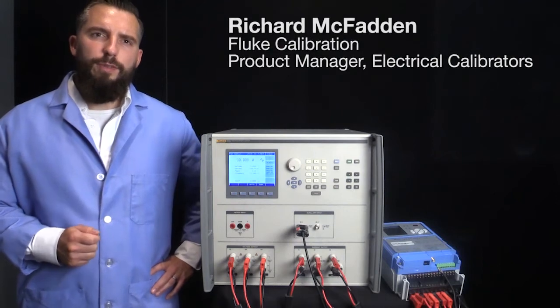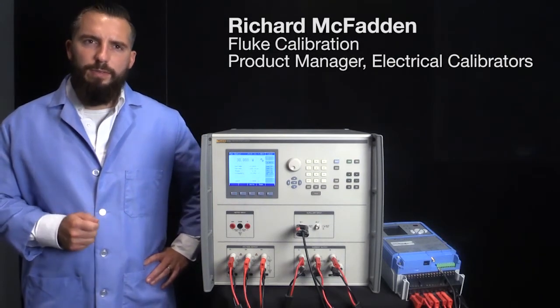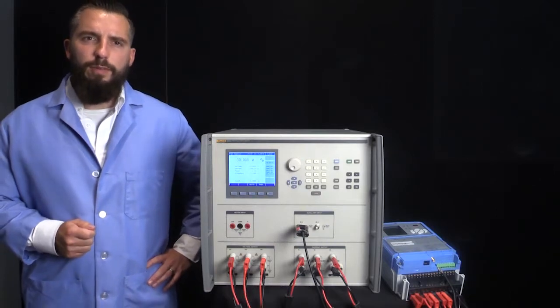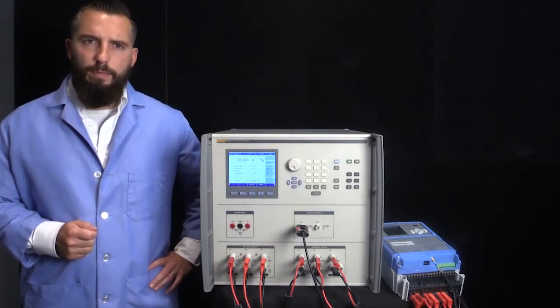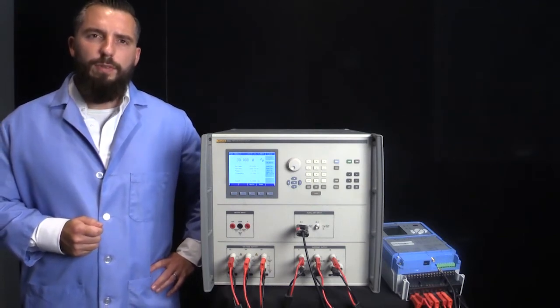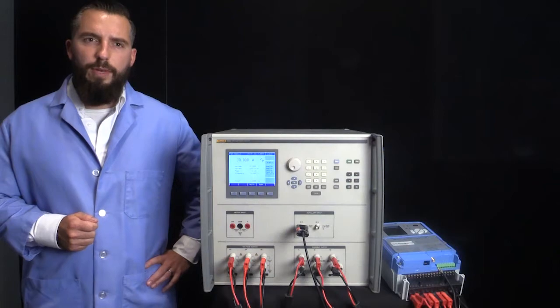Testing and calibrating three-phase energy meters can be difficult, time-consuming, and thus costly. This is mainly due to the process required to fully test and verify the output of the meter. Energy meters, almost without exception, use a technique of generating pulses to indicate the amount of energy they have measured.